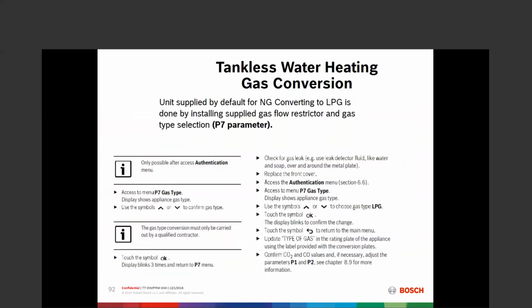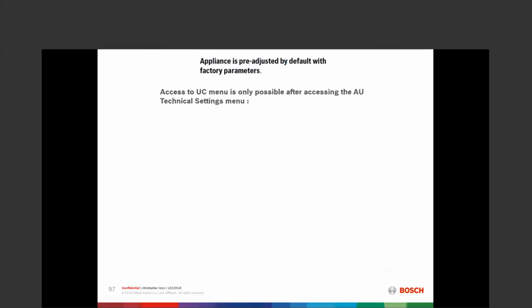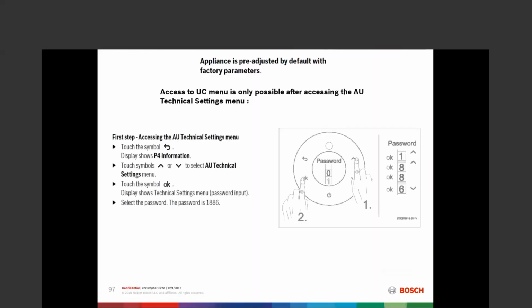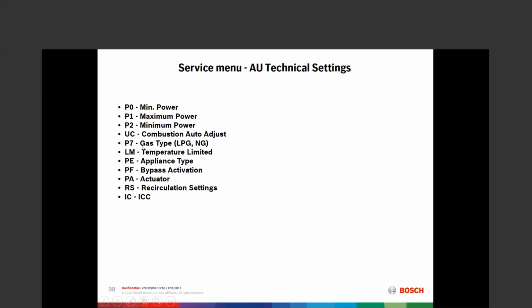Authenticate ourselves as a technician. So we're going to put in a passcode. That passcode is 1886. Scrolling through the menu, we go through authentication for technical settings. Scroll to 1, OK, 8, OK, 8, OK, and 6, OK. And that allows us to access those additional menus, including the menu P7, where we'll go in and change it from natural gas to propane gas. Press OK, and that converts it electronically.